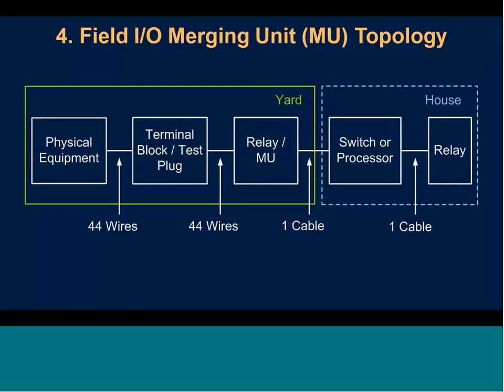The main focus of this presentation is this topology where we essentially have everything communicated over a digital signal. For these solutions, we wire everything in the yard to either a relay or a merging unit, which is the MU there. We'll touch on what exactly a merging unit is later on, but essentially all of the hard wires are out in the yard, and then that device will communicate through a fiber optic cable back to the control house. If it's a networked solution, it would be into a switch, or if it's a point-to-point solution, it would generally be to a processor on the relay.